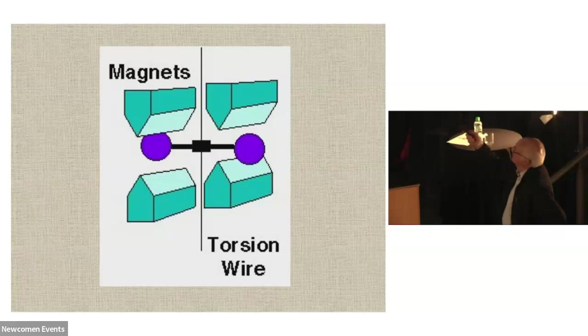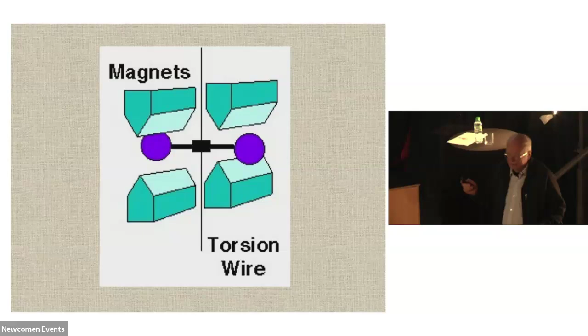And how he demonstrated this was that a strong magnet, which you can see the green bits there, and in the middle was a little dumbbell, and those two blue bits were filled with nitrogen, and it was strung with a torsion wire very lightly. So that if the concentration of oxygen increased in that magnetic field, it pushed the dumbbells out of the way. And he constructed a device to do it, made by a firm called Servomex.